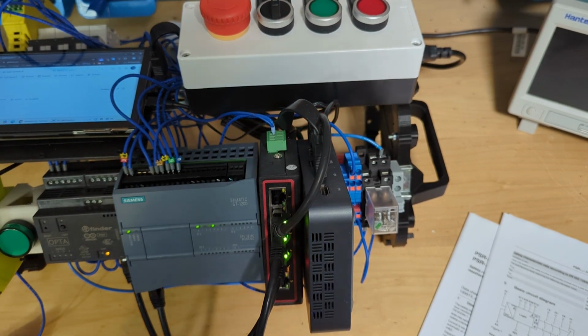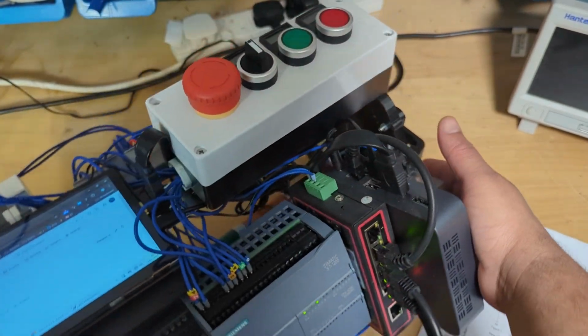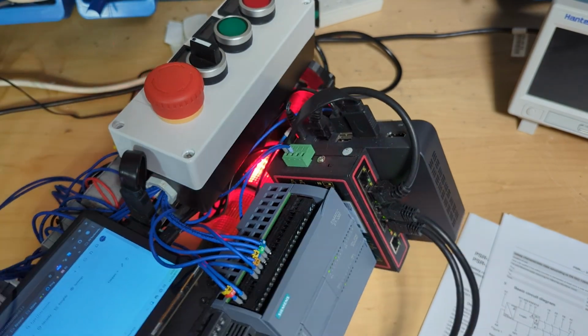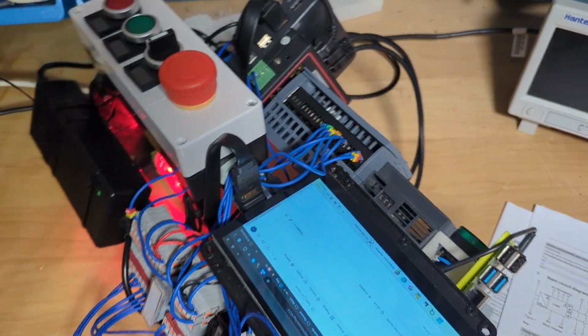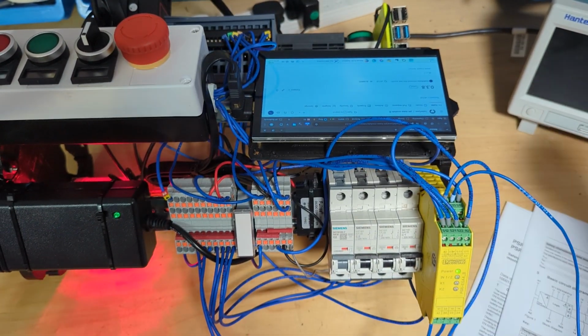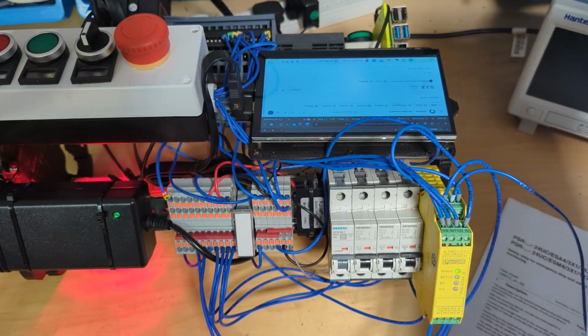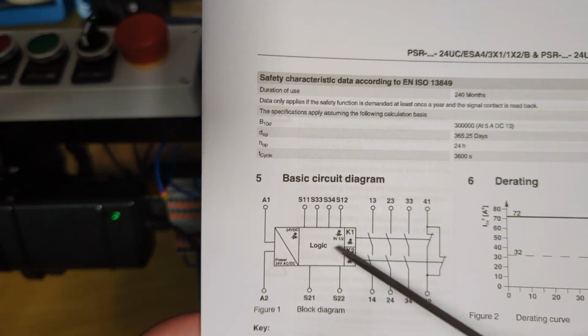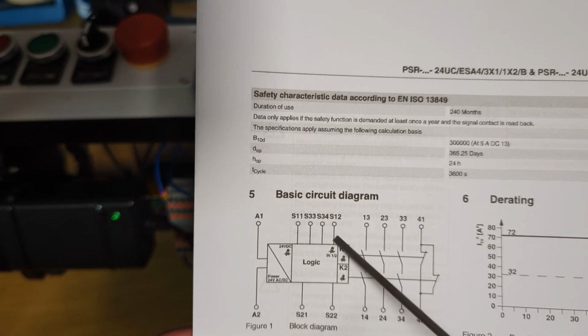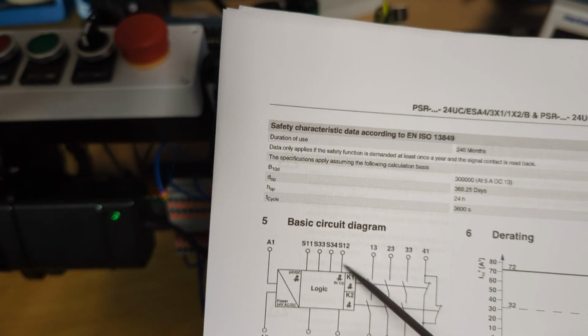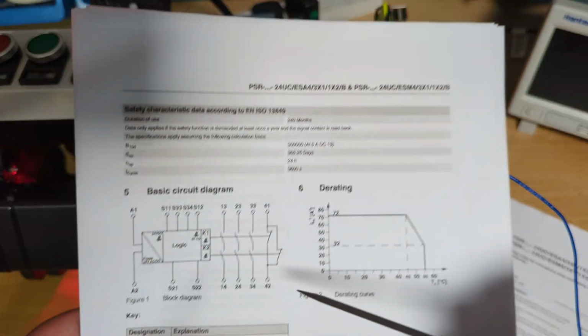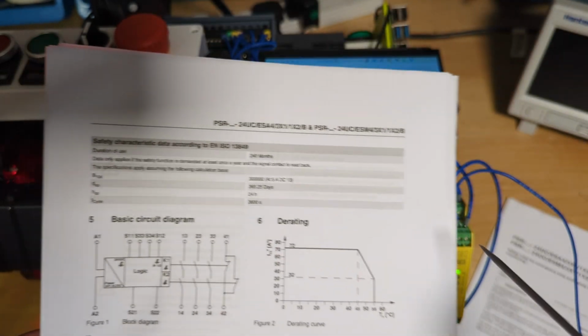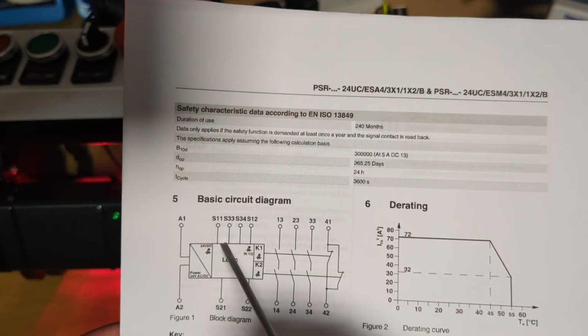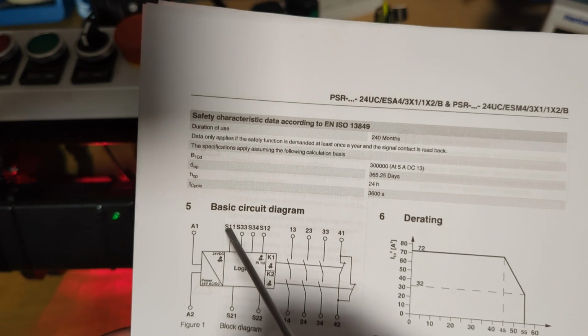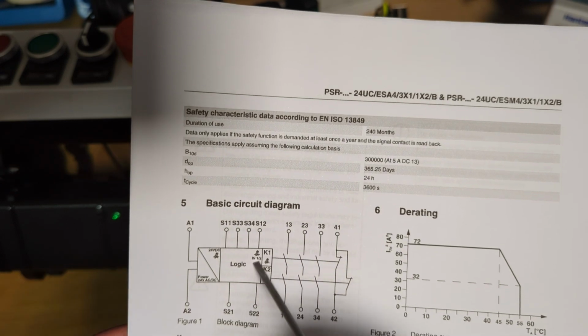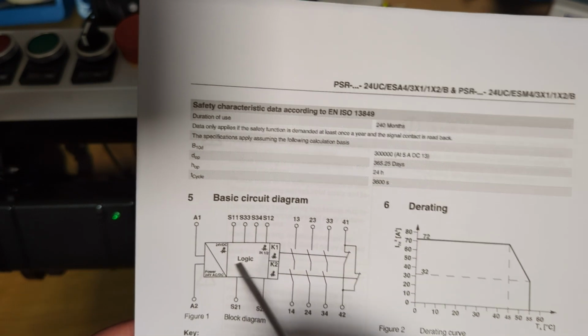The one thing to be aware of is that the safety relay I'm using doesn't have any monitoring, which is quite nice actually. The one I'm using at work does, and it's a bit of a pain because I want to play around a little bit and tap into this S11, S12 circuit. This one doesn't have any monitoring. So this e-stop relay is just looking for 24 volts. It goes, okay, S11 to S12, I've got a circuit loop there and I've got 24 volts.